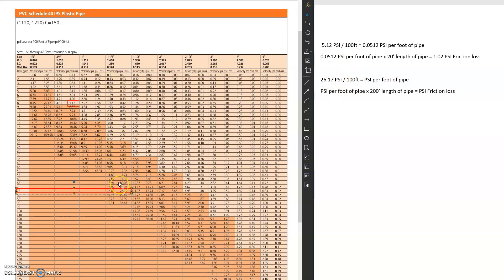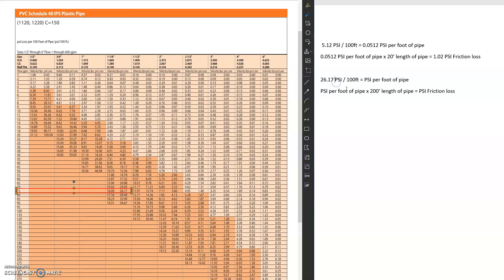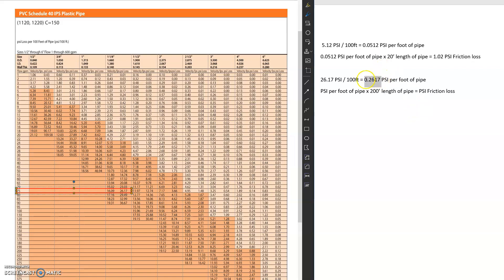As you can see, this pipe would not be sized correctly because we're definitely above the 5 feet per second. But let's say this was the case. So we can do the math of 26.17 divided by 100. We're literally just moving decimal places over. And then we're multiplying that by 200 because our length is 200.